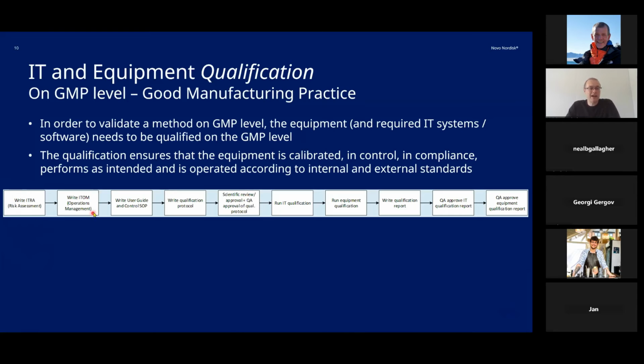And we have to write an ITOM, so IT operations management. We need to write very specific guides on what the user and method responsible should do in terms of operating the software. Because now if you have a method that works on an instrument and you change the settings of the method, then you are changing how the instrument works, how the instrument acquires data, and that will jeopardize, in principle, your results and the data that you get.